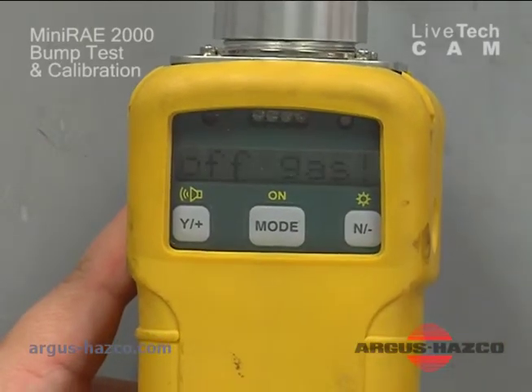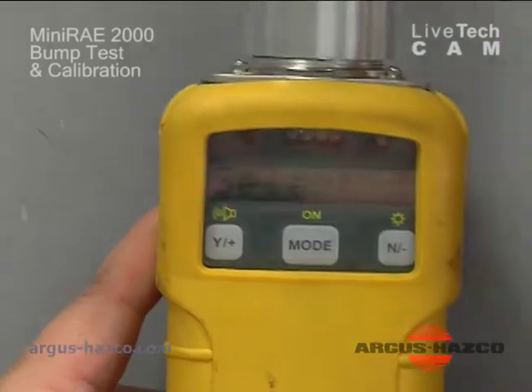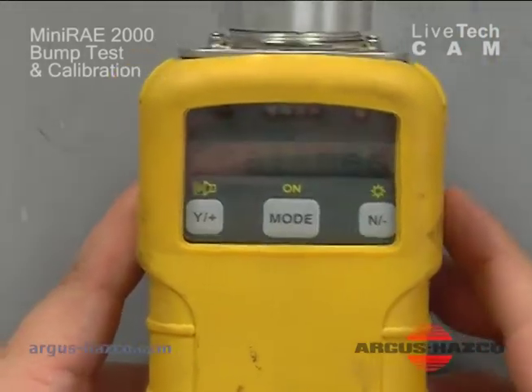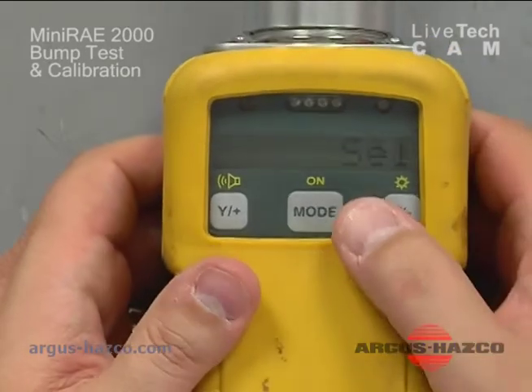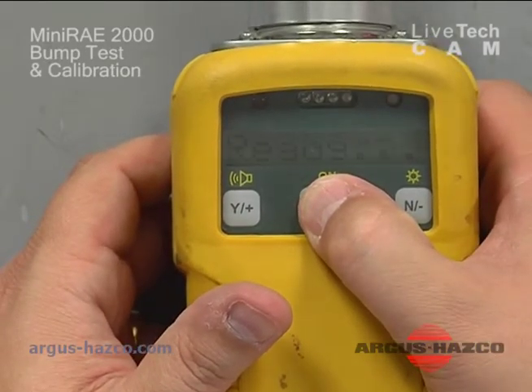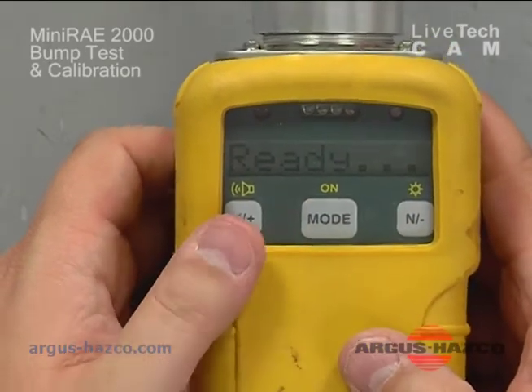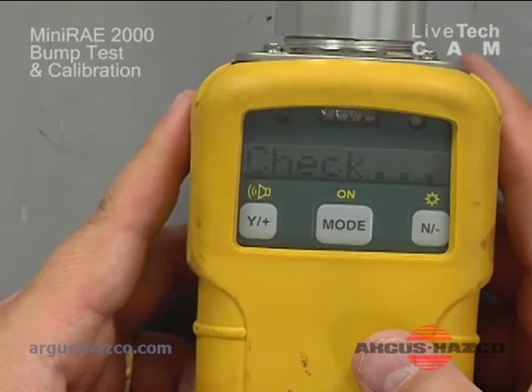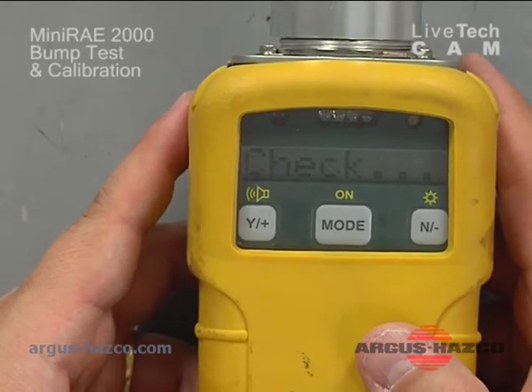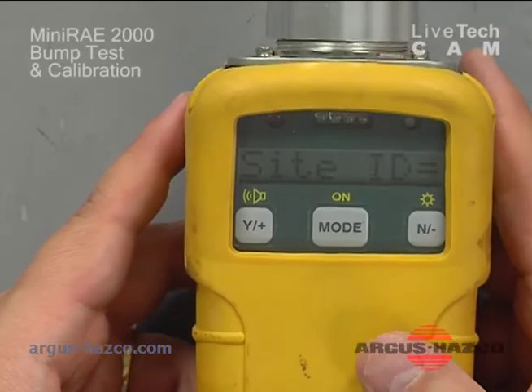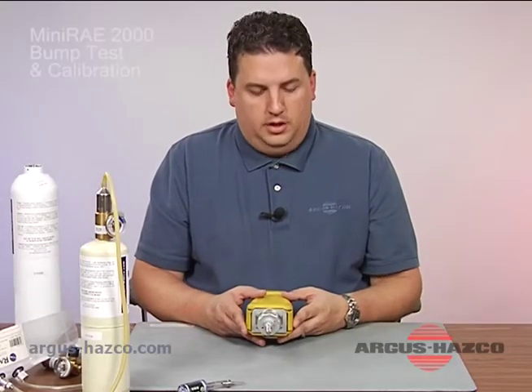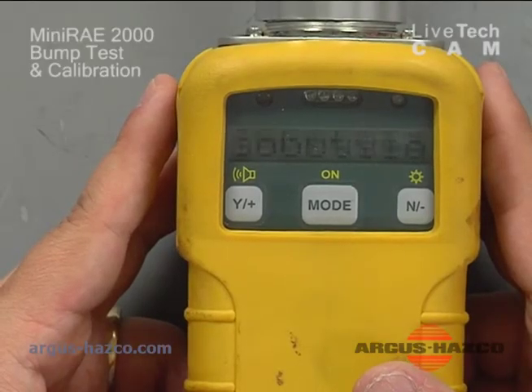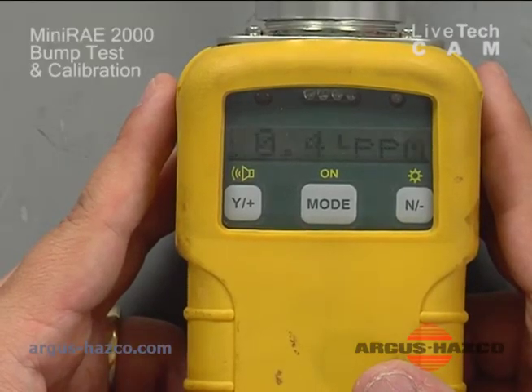Calibration done, and turn off the calibration gas. Remove the calibration gas. It's asking you want to select cal memory. At this point, you can press and hold the mode button. It'll get you back out to the ready screen. You can hit yes. It's going to go back into an operational mode and a survey mode. Again, giving you a site ID if you have one or assigned one. Warming up.